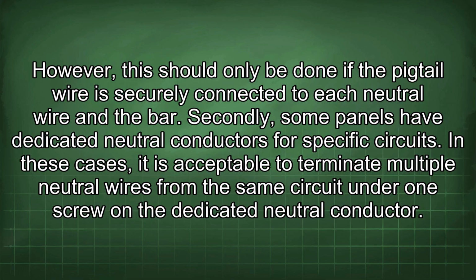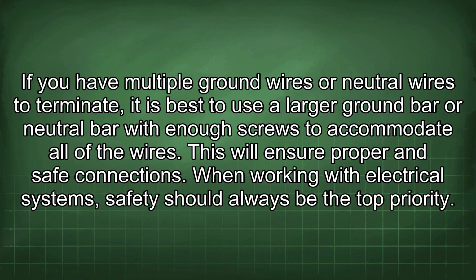Secondly, some panels have dedicated neutral conductors for specific circuits. In these cases, it is acceptable to terminate multiple neutral wires from the same circuit under one screw on the dedicated neutral conductor. If you have multiple ground wires or neutral wires to terminate, it is best to use a larger ground bar or neutral bar with enough screws to accommodate all of the wires. This will ensure proper and safe connections.